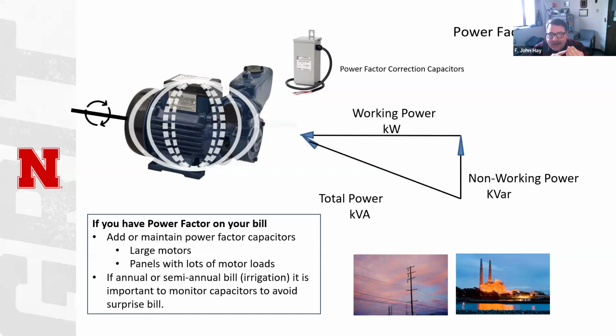So, obviously, trying to justify which is the right one to save. Power factor can add as much as $500 to an individual center pivot per year in costs if you have poor power factor. So it's going to be important to note: am I charged for power factor? Do I have power factor correction? Do I have the right power factor correction? Is it functioning? That's going to be a very quick savings, as much as $500 a year, with an investment that may not be too significant. Now, these power factor correction devices can cost $200 to $500 themselves, but if you're saving up to $500 a year, that pays for itself pretty quickly.